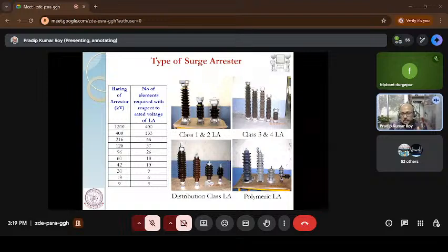So the requirement from the industry has come: how can we reduce the height of the surge arrestor though the rating will be the same? For example, for 400 kV, if you look here, we are using 133 ceramic blocks. If it is a 1200 kV surge arrestor, they are using 400 blocks. So there is a stacking of 400 blocks. The height is so high that this normally never passes the seismic test.